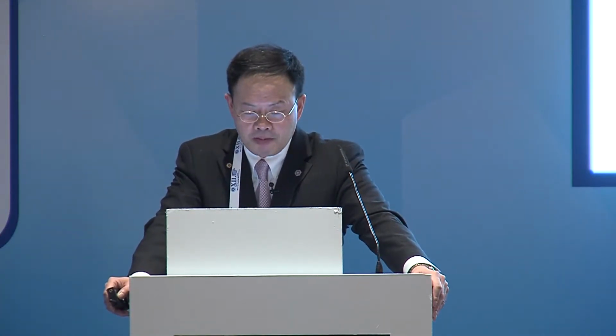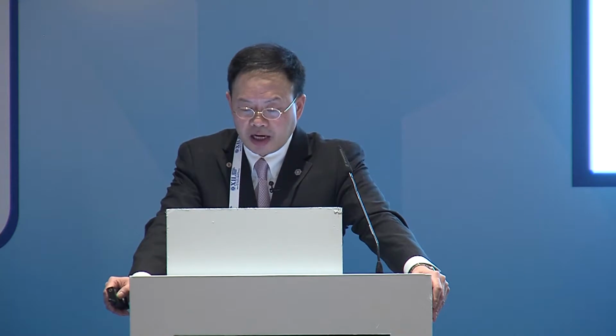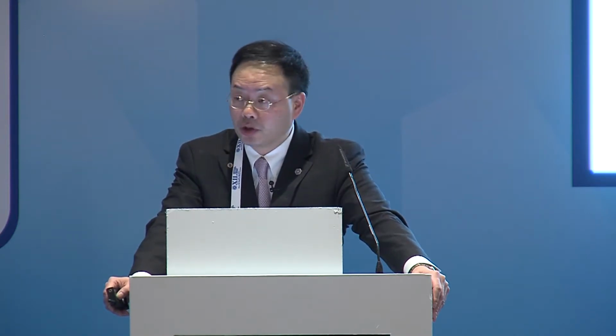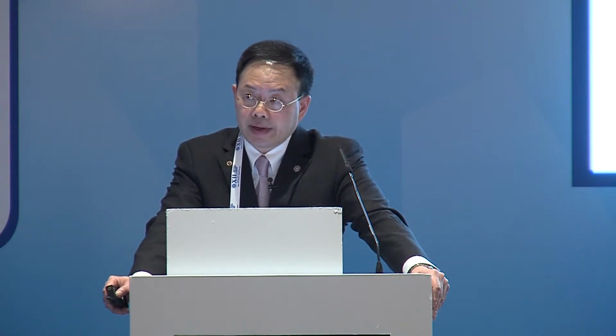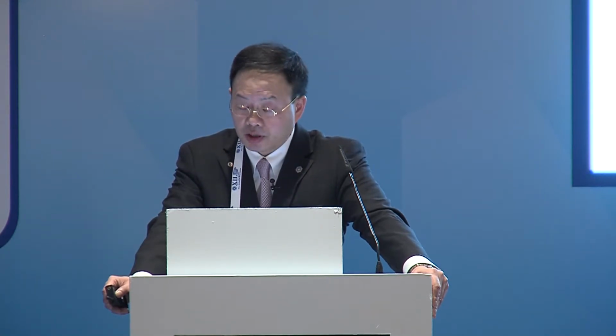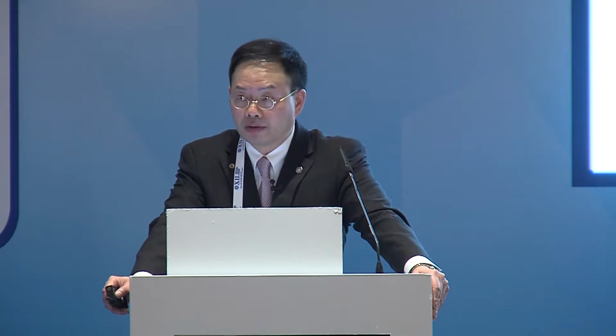As the IEST president-elect, I'd like to share the background in the US on how we decided the air change per hour for each class. This was a table IEST published for almost 2 decades, before 2013. In this table, IEST is saying, if you want an ISO 8, we recommend an air change per hour of 5 to 48; for ISO 7, 60 to 90. And if you want to design ISO 2 or cleaner, the air change rate is 360 or higher.